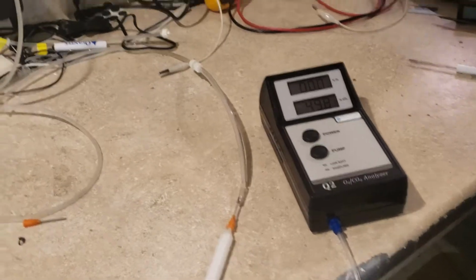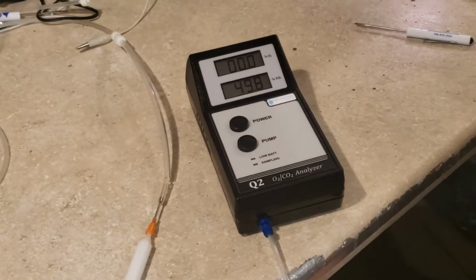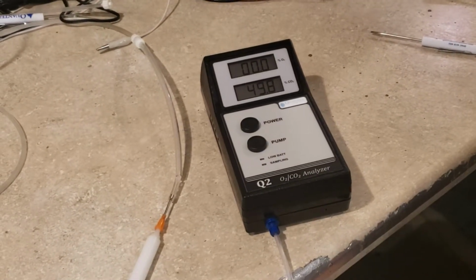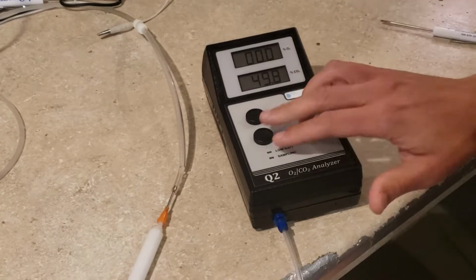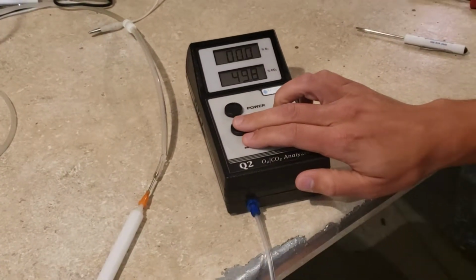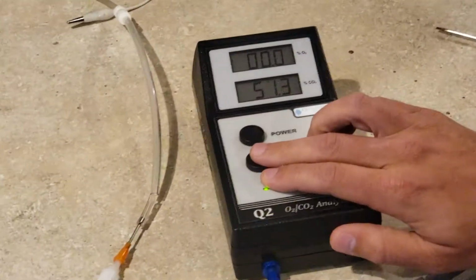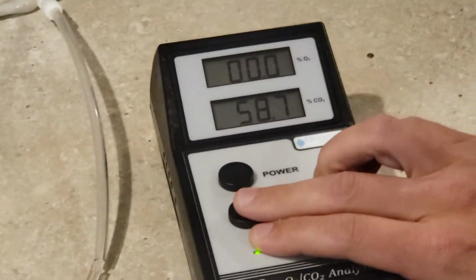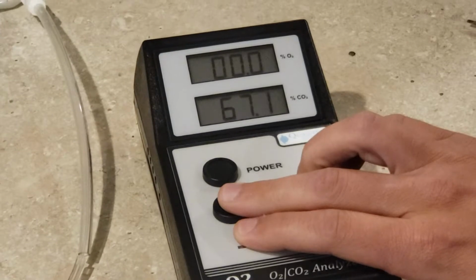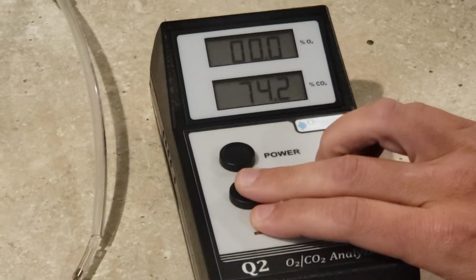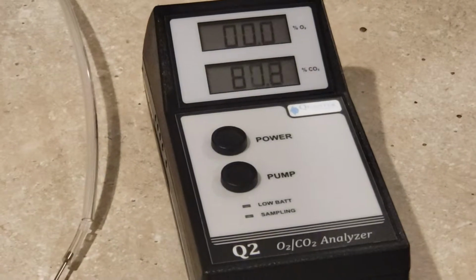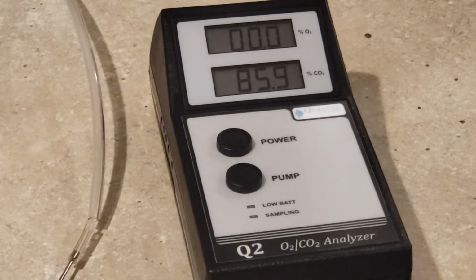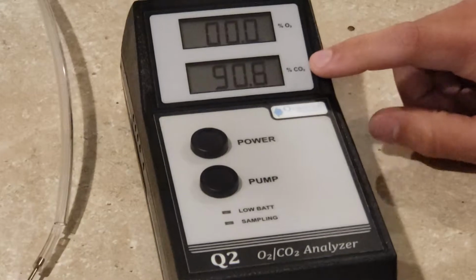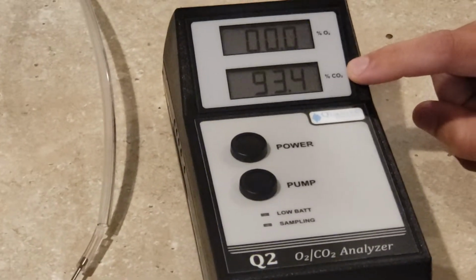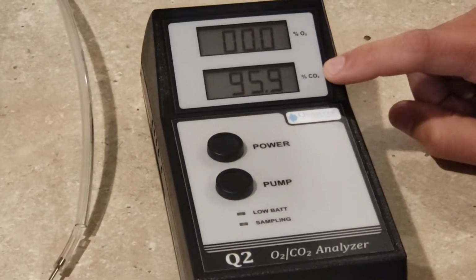So right here, I'm going to turn on my 100% CO2 tank. And the oxygen should, again, stay pretty close to 0. So I'm going to go ahead and pump this at 100%. And the oxygen is staying at 0, which we expect, and this is climbing up towards 100. So we're going to wait for this to stabilize and see where it ends up.